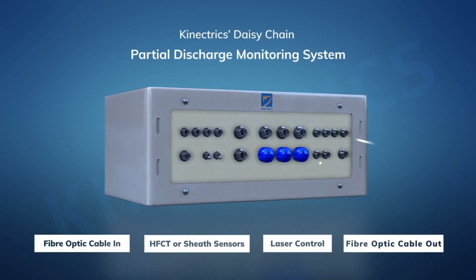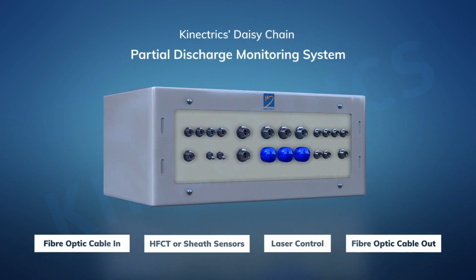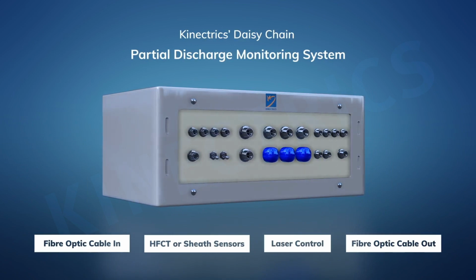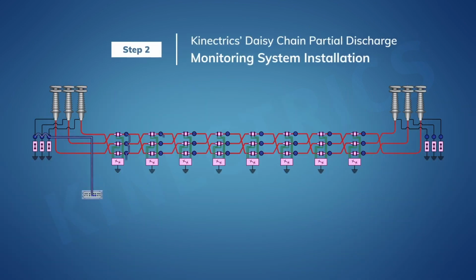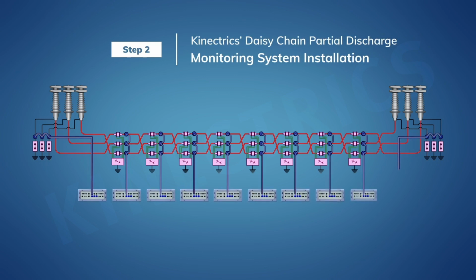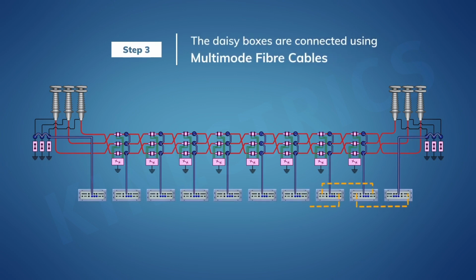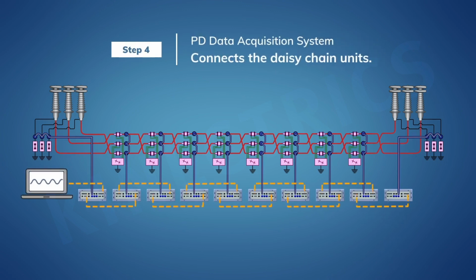We're going to do this all by remote control. So having installed those partial discharge sensors, we're going to install our daisy chain unit. This is a remote controlled, battery powered switching unit. So during the test, the engineer, having completed the test on one phase, can now configure that network of daisy chain units to switch automatically from the phase we've just tested to the next phase we're going to test. And this saves us manually doing the switching. It's all done by remote control in a much more timely way.